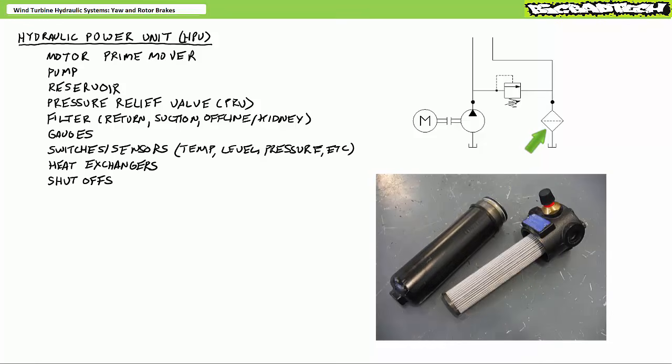The hydraulic power unit will also most likely feature a return line filter, positioned such that any fluid routed through the system must go through the return line filter at low pressure prior to being emptied into the reservoir. The fluid in the reservoir is then allowed a chance to cool, settle out any remaining particles, and dissipate any entrained air before it's pumped back into the system.